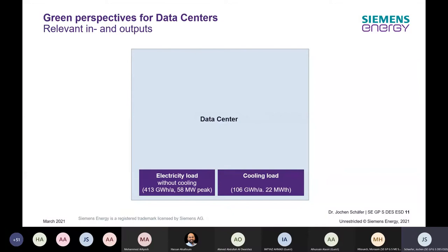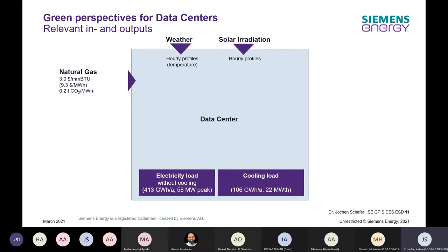When starting such a process, it's always important to have a common understanding of the relevant inputs and outputs. The data center has an electrical load and a cooling load that must be met at each point in time. We consider significant solar potential, weather conditions — especially ambient temperature's impact on the chiller's coefficient of performance — and natural gas price along with its emission factor.